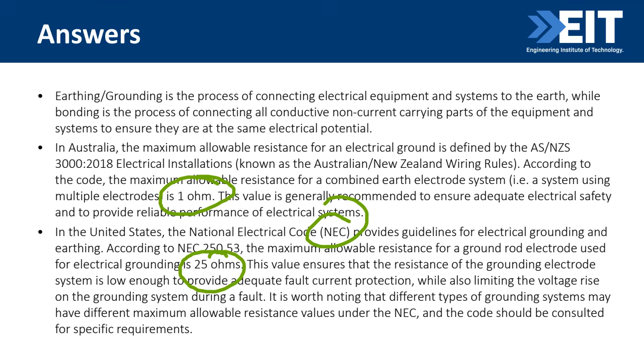And in the States, 25 ohms under the NEC code. So it's high, obviously 1 ohm is not a good one, you want it 0.1 or 0.01, but that just gives you an example of the resistance. Why would the US be 25 times higher? That number is the maximum, and the NEC code actually defines each individual area with specific numbers, which I haven't quoted here, so it's actually a lot more complex. As Pete said, everything's bigger in the USA.